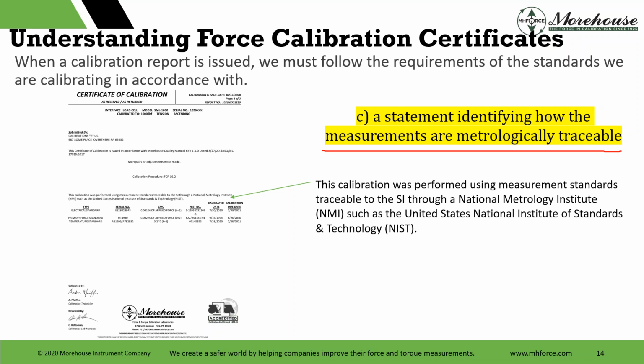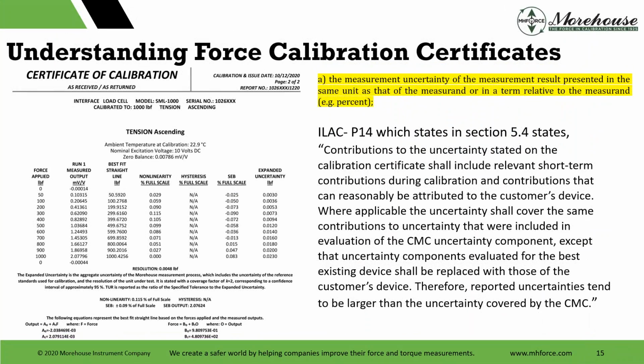It would be best if you also ask how far away the lab was from NIST in regard to metrological traceability. Remember, we had that pyramid, and the further away one gets, the larger the uncertainty becomes. So someone could be 4, 5, 6, 7, 8, whatever it is away from this, where their uncertainty is very, very large. So you really need to look at the lab scope of accreditation and make the appropriate determination if that laboratory that you're choosing to send your equipment to has the capability to perform the calibrations as required and as you need. Because the one thing you cannot have, you cannot make a better measurement uncertainty-wise than the lab that performed the calibration on your references. You may be able to make the better measurement, but uncertainty-wise, mathematically, it does not work. Every level down, the further you are away from SI, the larger the uncertainty becomes.